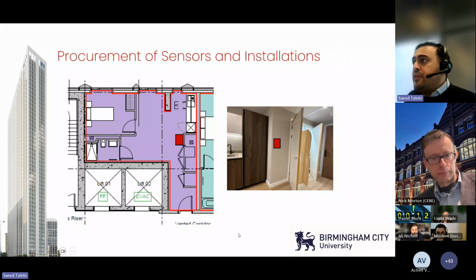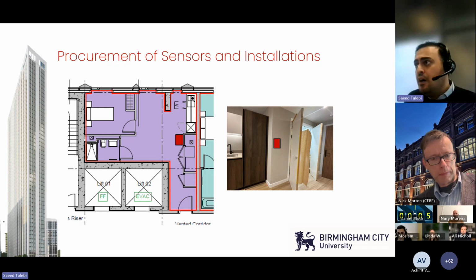A key part of effective deployment is the placement of sensors within each apartment. For accurate reading, sensors need to be installed at a specific height, normally between 1.2 to 1.6 meters above the floor, around breathing level, and must be positioned away from entrances or direct sources of heat like ovens or radiators. It's crucial to get these details right at installation, because it ensures that the digital twin operates on trustworthy data, and it reduces the need for costly repositioning later.